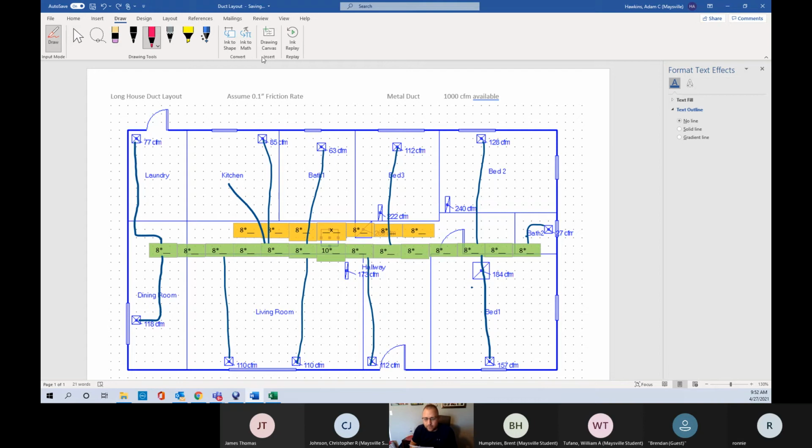Now, could I move more? Take your slide rule to 10-inch. Go to 10-inch diameter, round, in the middle. Okay, how much at 0.1 would a 10-inch flex move? 425. Or a 10-inch round, yeah. At 0.1, about 415, 420 CFM. Now, what if I go down to 0.04? What will it move? 250. Right around 250. All right.